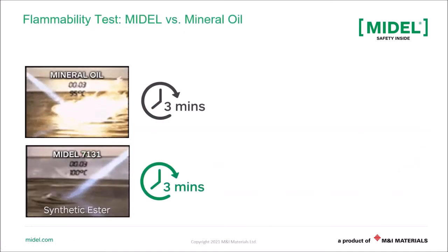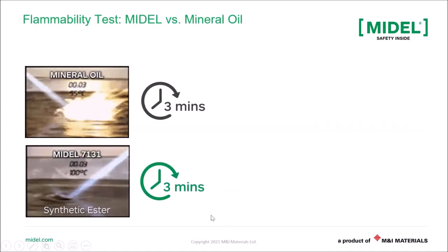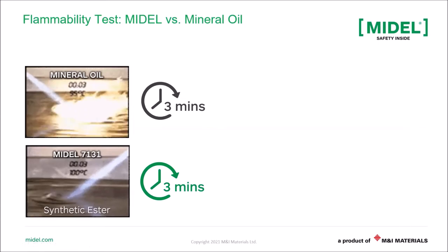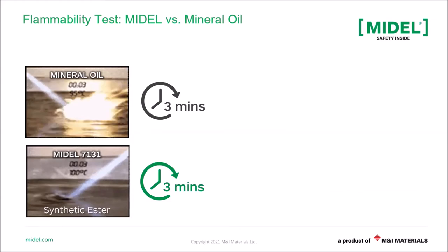So what I wanted to show you was a test that is done on flammability of MIDEL ester liquids in comparison to mineral oil. Now, there are many tests like these. In fact, there are tests that have been done to simulate leaks inside a transformer, tank ruptures, as well as trying to light the whole transformer on fire. And in all those situations, it's evident that ester liquids are fire safe in comparison to mineral oil.